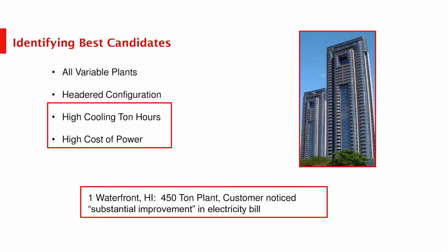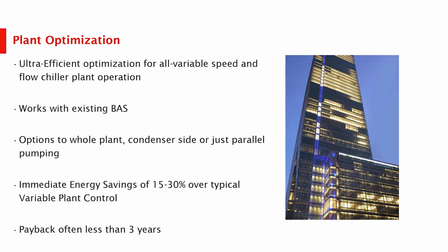Of course, there is always an exception. In the unlikely event anybody actually is familiar with this building, they only have one chiller. This is a one chiller application, which normally I would say, probably not the best candidate. They, however, save a lot of money simply on the condenser side optimization. And they were very happy, continue to be happy, and they noticed a very substantial reduction. So while there are obvious choices or obvious places to start, clearly there's some candidates that should not be overlooked.